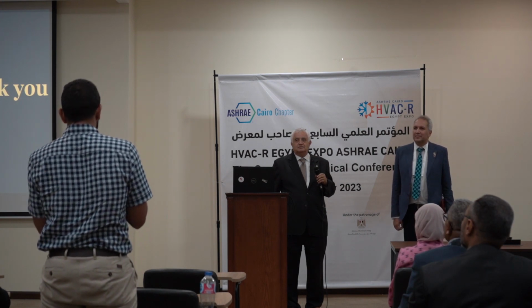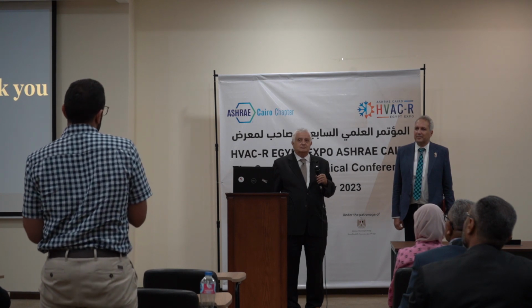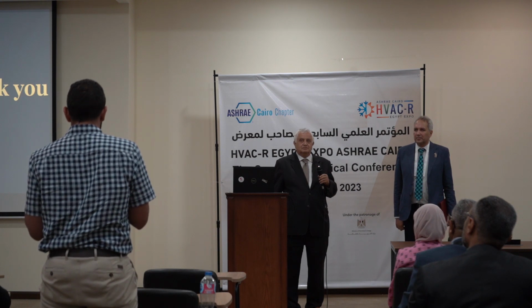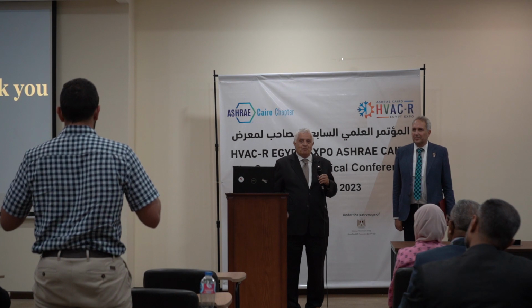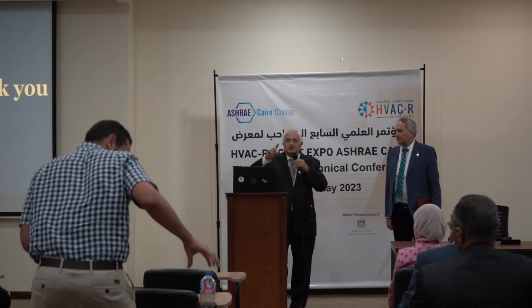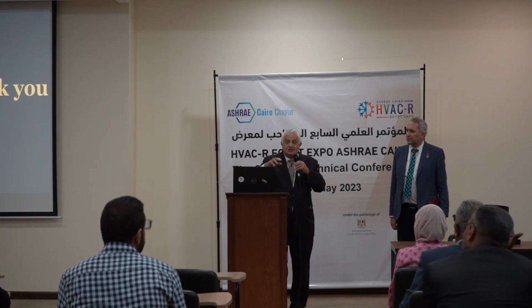I'd like to ask a question about the performance of the machine. We compared the capacity of both machines and found it comparable, but what about the sensible heat ratio or sensible heat factor of the machines? Does both machines cover the related load in the same magnitude, or is there a difference? You cannot compare the heat ratio of an IEC machine with a DX machine simply because the process is different. You are cooling first adiabatically, and then cooling along a constant dew point temperature line, so it's sensible cooling at the first stage. Then there's humidification at the second stage with a bit of cooling, and then at the third stage, the DX coil inside the machine provides another stage of cooling. So the heat ratio differs, but in the end, the overall refrigeration capacity is what really matters more than anything.